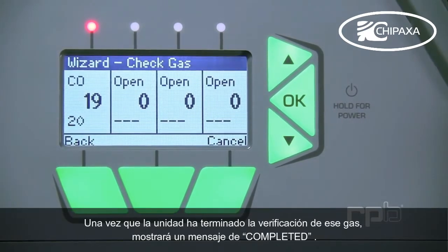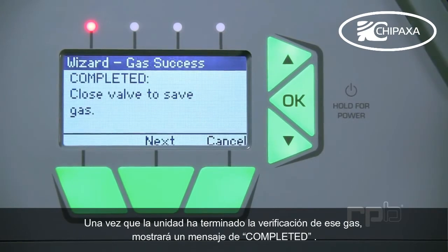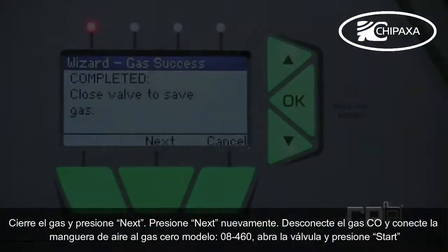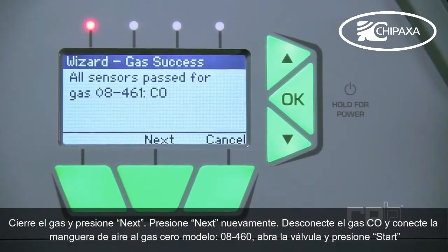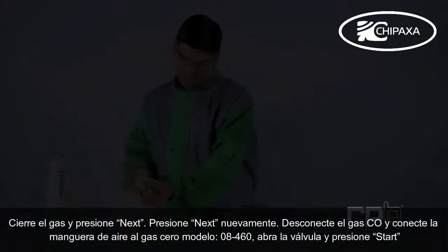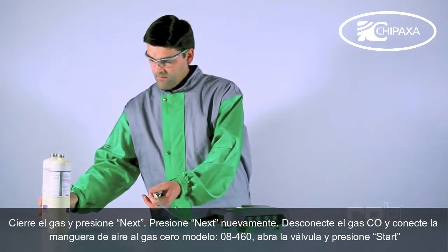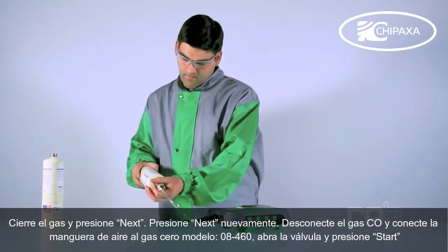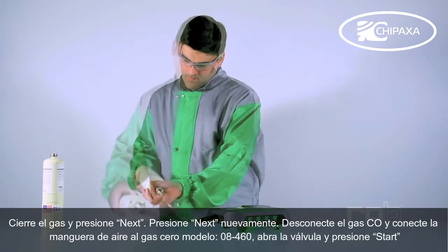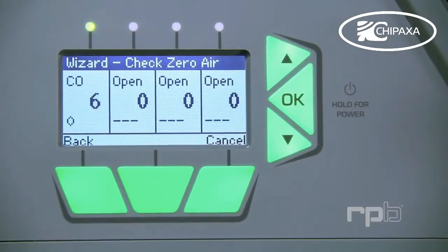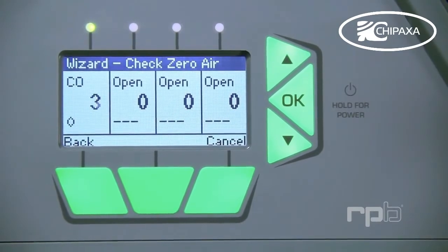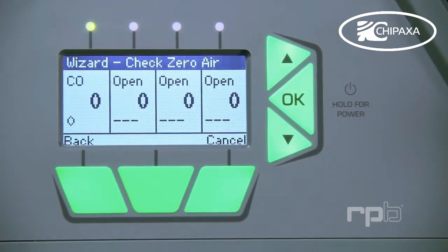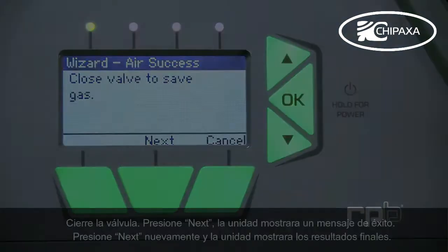Once the unit has passed the check for that gas, it will display a completed message. Turn the gas off and press Next. Press Next again. Disconnect the CO gas and connect the air hose to the 08-460 Zero Air. Open the valve and press Start. Close the valve. Press Next.